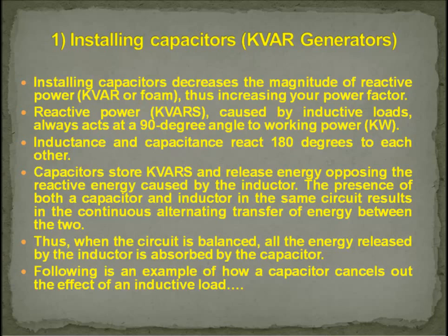Capacitors store kVARs and release energy opposing the reactive energy caused by the inductor. The presence of both a capacitor and inductor in the same circuit results in the continuous alternating transfer of energy between the two. Thus, when the circuit is balanced, all the energy released by the inductor is absorbed by the capacitor. Following is an example of how a capacitor cancels out the effect of an inductive load.